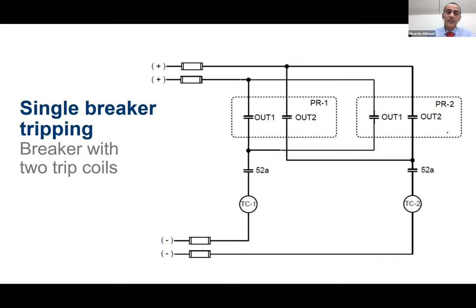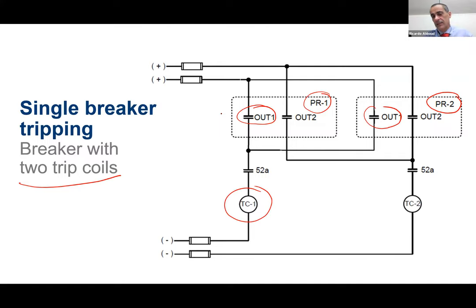Okay. So this is a single breaker with two trip coils. It's common for transmission breakers to have two coils. Okay. In this case, it's one example with cross tripping. So I'm tripping coil one with protection relay one, that is the main one, and protection relay two, that is the main two. So I'm tripping trip coil one with those two output contacts directly. I don't need an auxiliary relay here. Okay. And same for trip coil two.